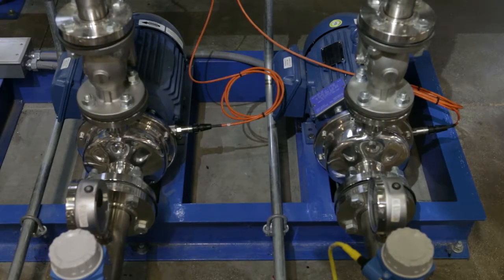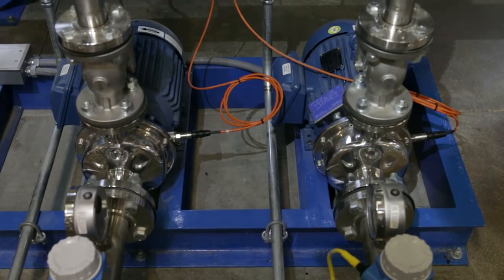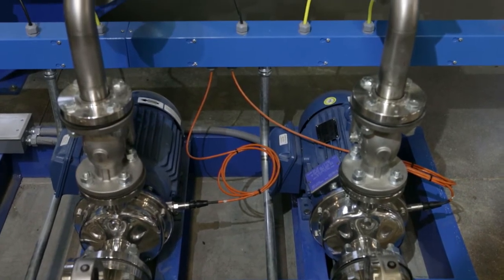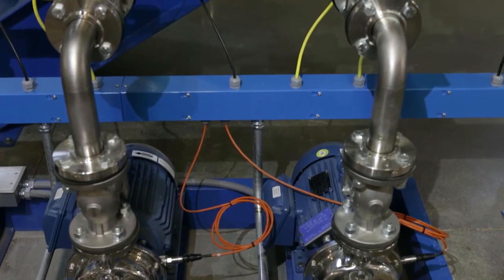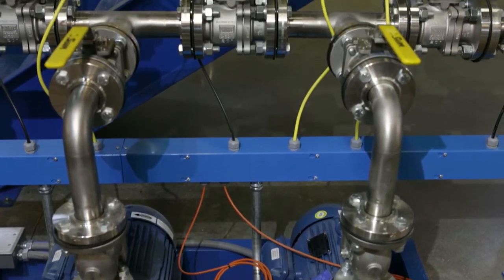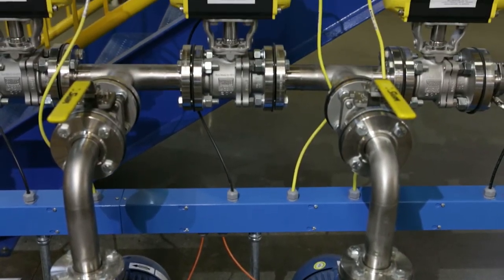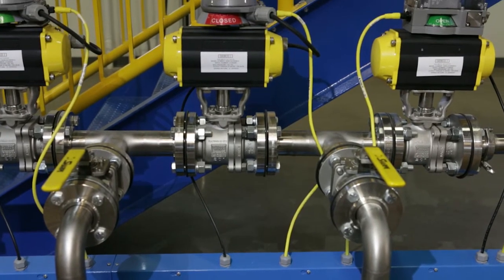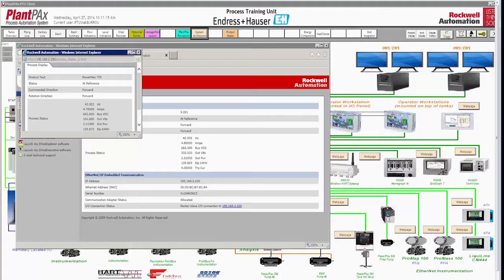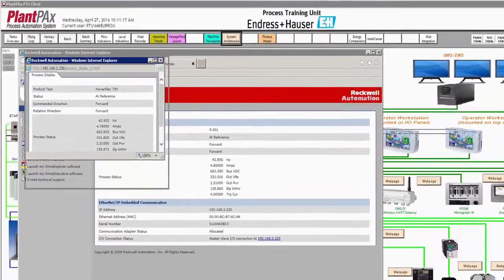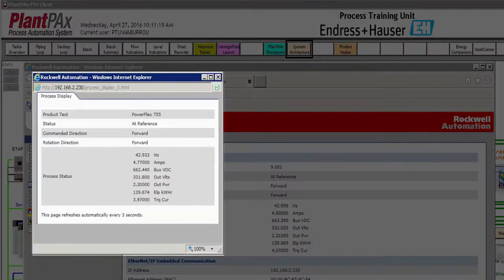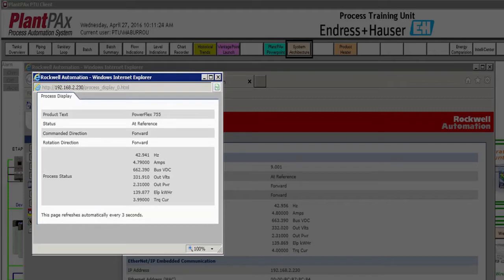Now, pump 2 is powered by an Allen Bradley PowerFlex 755 AC drive. There is no control valve installed to control the pressure or flow rate. In this PID loop, the PowerFlex 755 controls the speed of the pump to maintain the line pressure instead of opening and closing a modulating control valve.